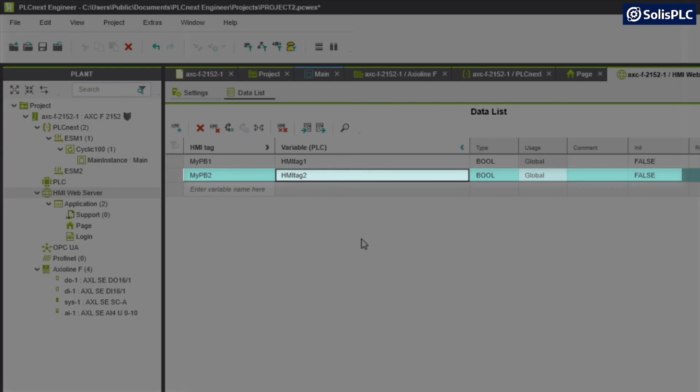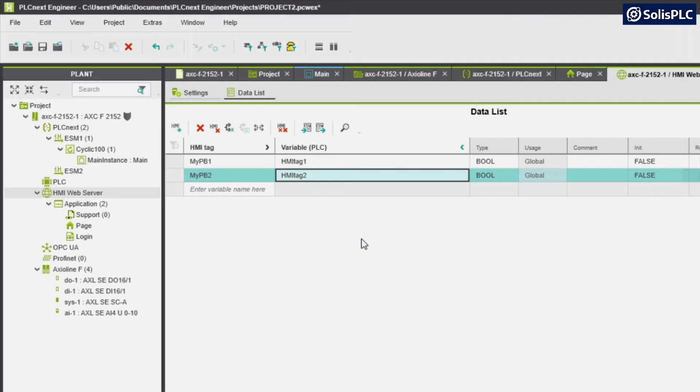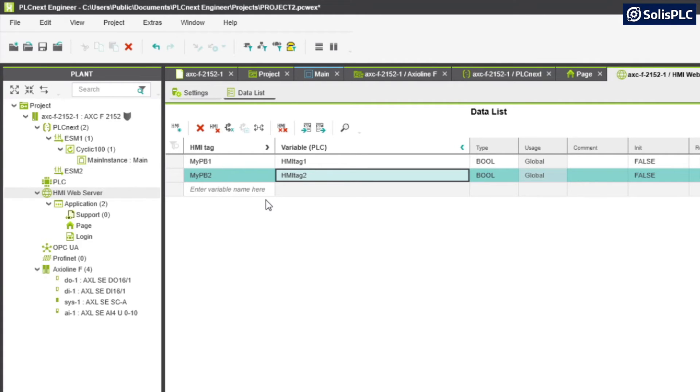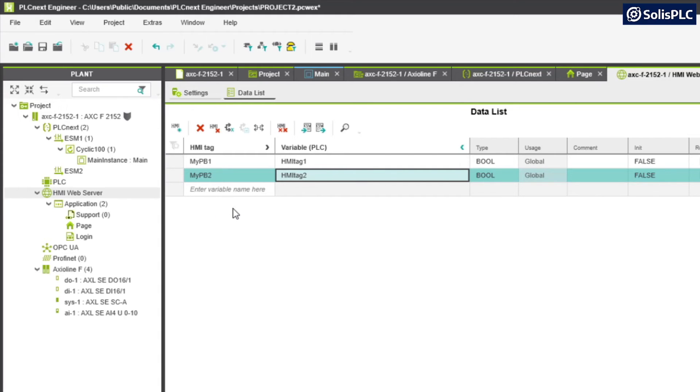This is how you make the link between the HMI application and the PLC application. You'll notice that the PLC tags that are not necessary for the HMI application are not going to be tied back. In a way you can limit the scope of some of your tags and not recreate all the PLC tags on your HMI side.